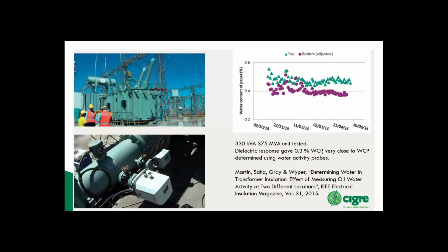So what we did was we took the water activity measurement from both of them, converted it into the water content of paper, and then again we did our adjustment. In this case, the probe at the bottom is the one we want to adjust more, because we want it to be more reflective of the temperature within the tank. The temperature being measured at the top of the tank is probably going to be pretty close to the temperature of the winding, just from that flow of oil going around. So we got quite a good close correlation there, not only between the 2 probes, but also with the dielectric response. They were showing pretty much the same value.